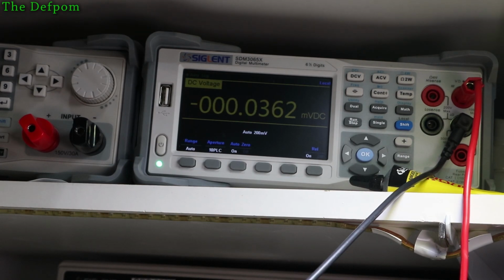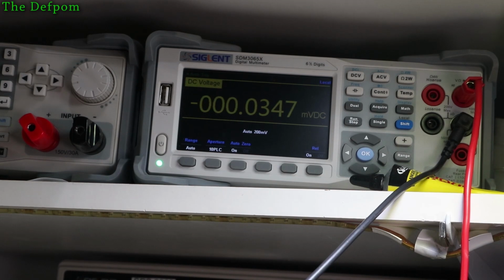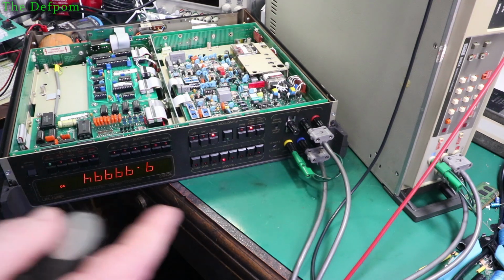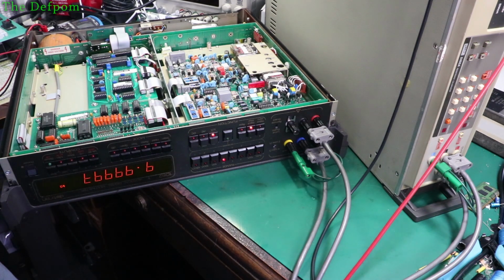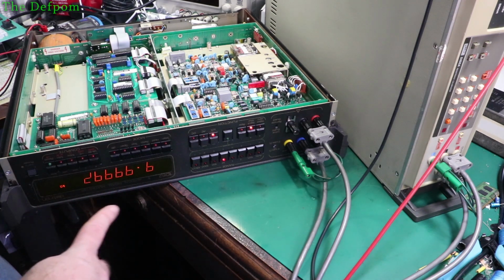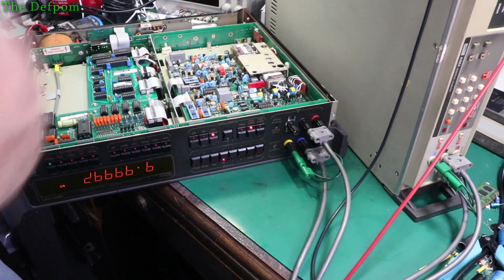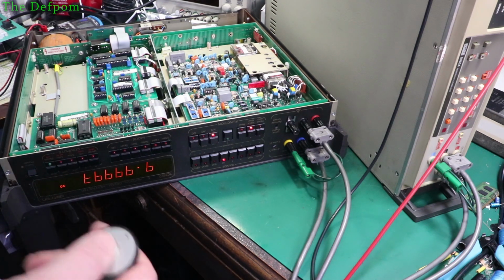I don't think I should be getting an error message for that, but I'll try. I'll take everything off now, put the cover back on, give it a few minutes to warm up again and settle down, and we'll do a retest. Doing those adjustments does seem to have made a difference. I'm now getting a slightly different value here compared to what I was getting before. So yes, I will need to recalibrate the ohms board, but that's not a big deal.